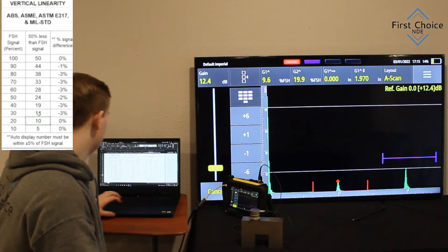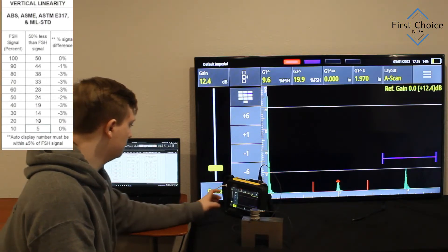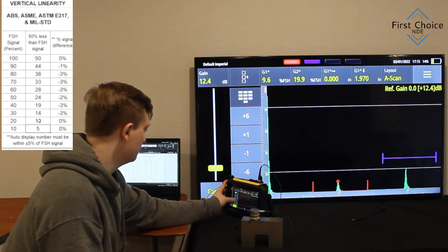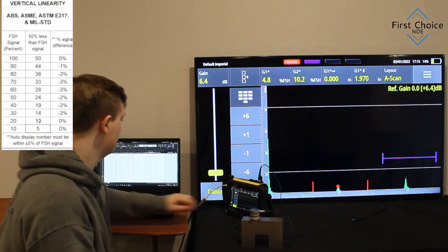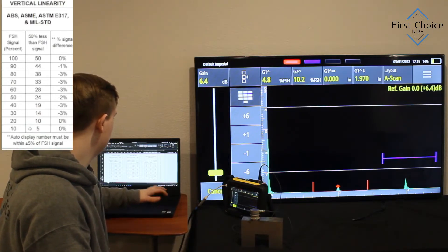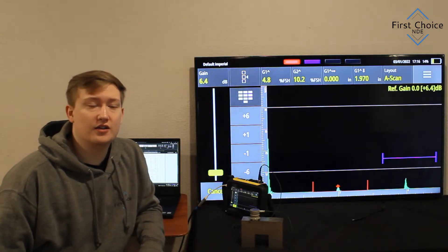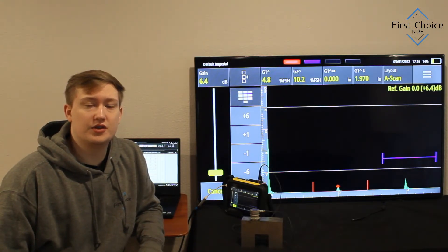Here's the 20% on the right, and we have 9.6 roundup to 10, so 0%. So that's perfect. Then you would go again, so we have 10 on the right, 4.8 roundup to 5. Alright, and as you can see, that concludes the vertical linearity, and it is within calibration.